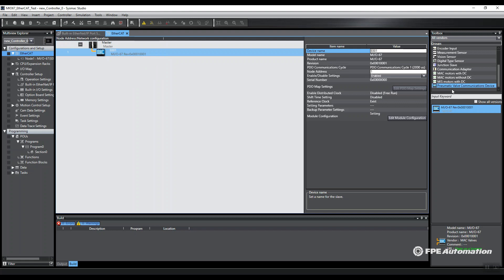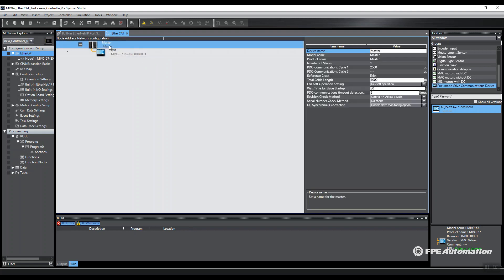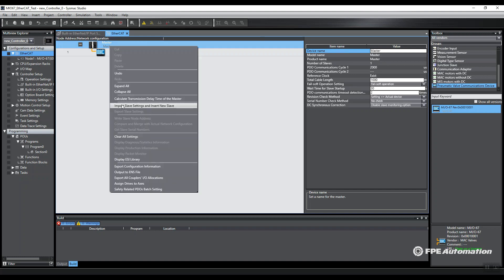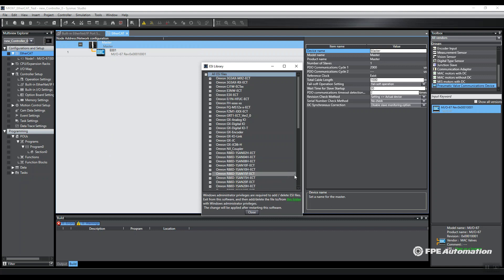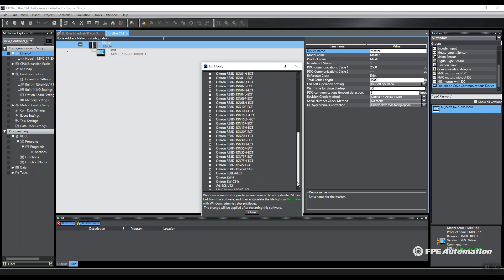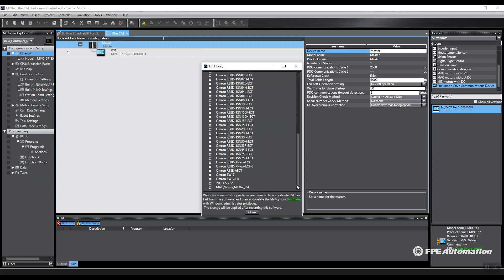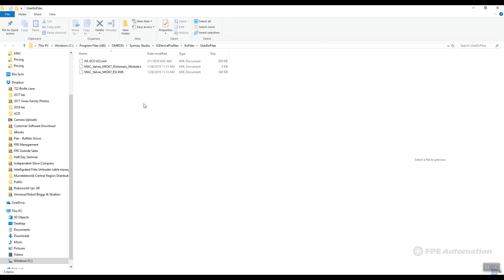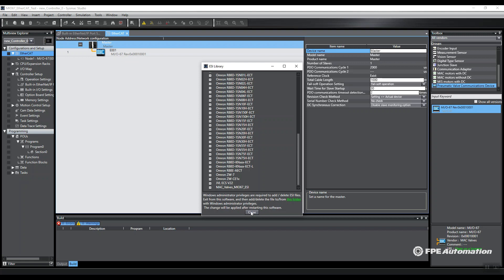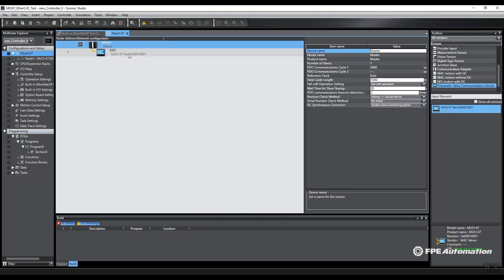If I don't have the icon for a Mac pneumatic valve communications device, I want to first go to master, right click, go to display ESI library, and then I would download the ESI file from Mac's website or your local distributor and paste the file into this folder here. I paste it in here and I restart Sysmac Studio, and I should have access to this device.